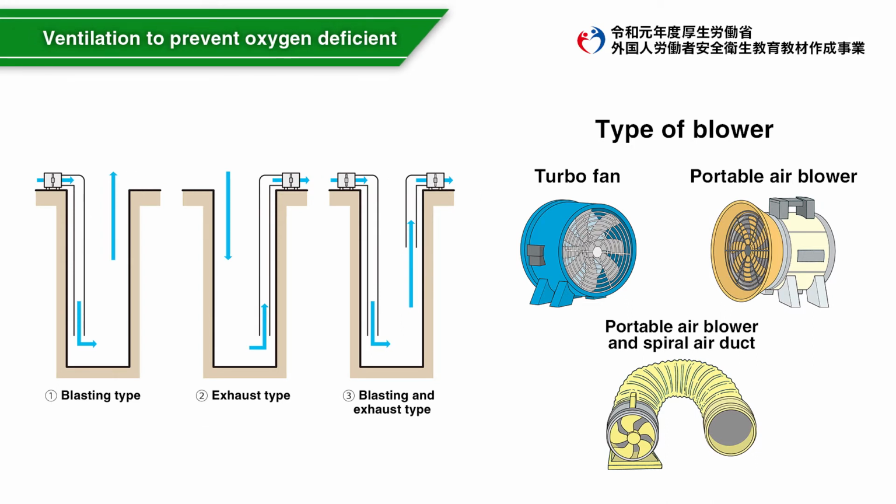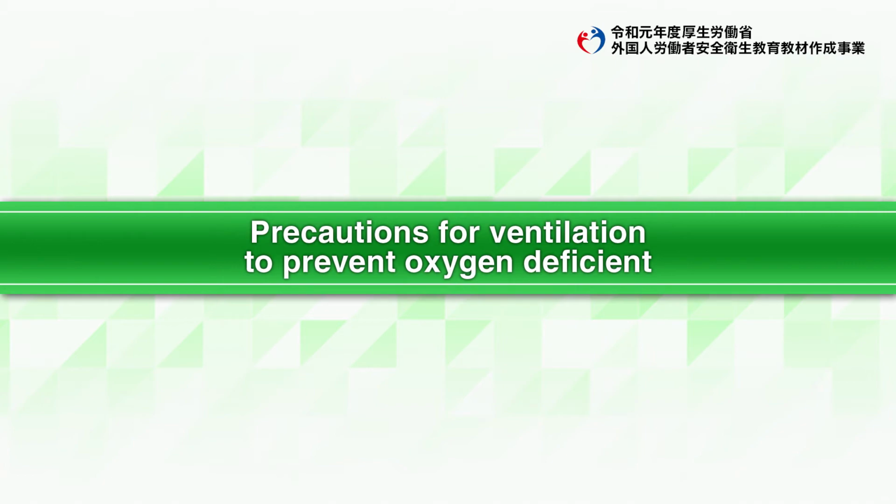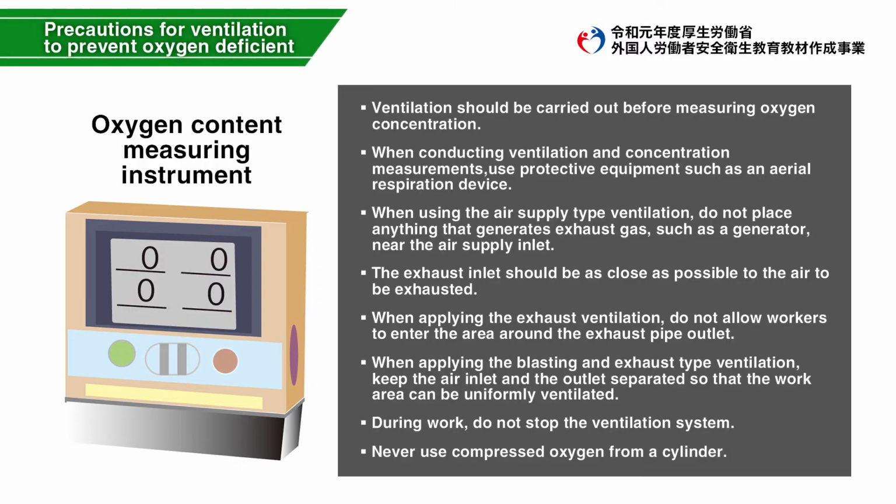Ventilate the oxygen concentration of the workplace when carrying out oxygen-deficient hazardous work, unless it is not possible to ventilate to prevent explosion, oxidation, etc., or it is extremely difficult to ventilate due to the nature of the work. Oxygen concentration must be kept above 18%. Ventilation is conducted using a blower such as this. Ventilation is conducted under the direction of an operation chief, but a worker must also understand the basics.